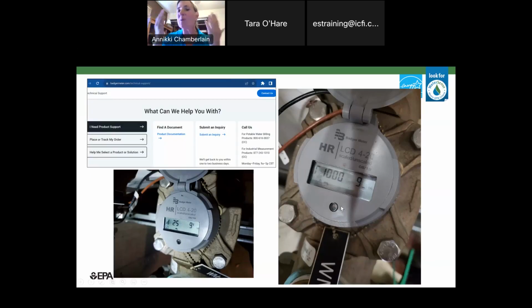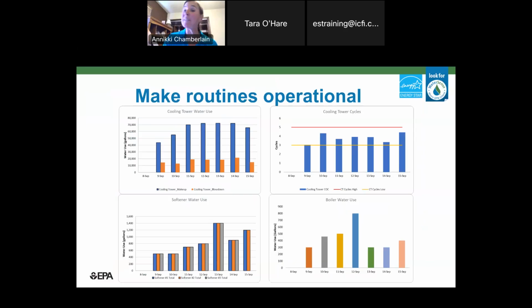So even though we got a good procedure, a beautiful new tower, the data is meaningless because we're not using it. So we get the right program in there, and then we take all of their forms and we incorporate it into one form that they can fill out on a tablet that automatically calculates meter reads, plus makes everything graphical. So now they can see their cooling tower makeup and blowdown, automatically calculates their cycles of concentration. Plus we were able to include water softeners, boilers, tons of stuff.